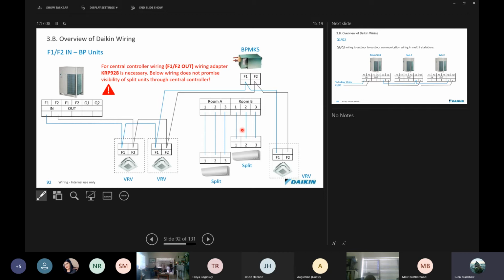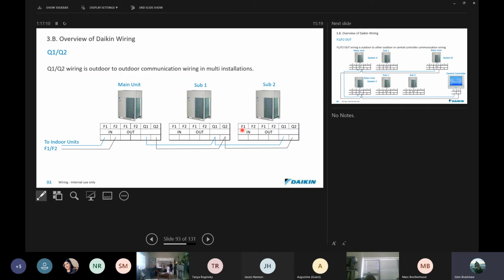All right. Q1, Q2, what is that used for? Well, that's the outdoor wiring. This is when we have more than one condenser. We have 1 or 2 slaves connected to it. And the Q1, Q2 also daisy chain from the master to slave 1 and to slave 2. So just keep that in mind as well. These cables must be in.